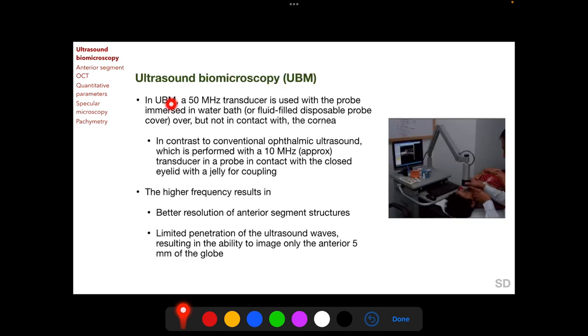Whereas visual field testing allows functional assessment of a glaucoma patient or suspect, imaging devices allow structural assessment of various ocular structures. In ultrasound biomicroscopy, a 50 megahertz transducer is present in the probe, and during examination the probe is immersed in a water bath or covered in a fluid-filled disposable probe cover and kept over but not in contact with the cornea.